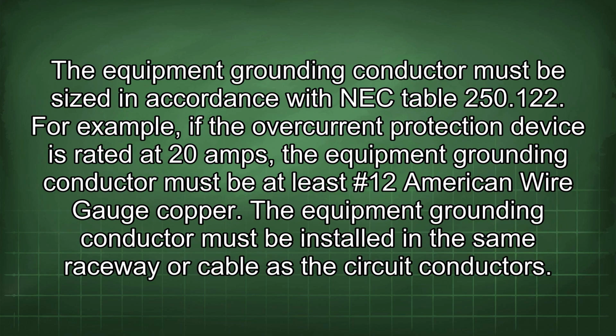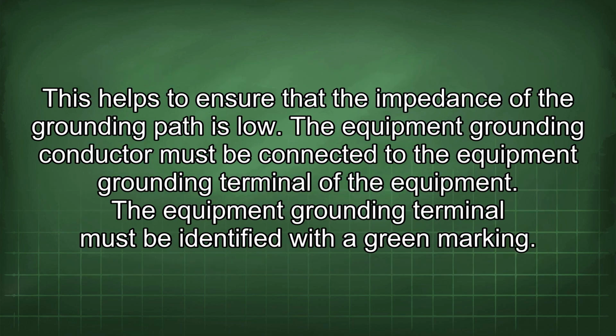The equipment grounding conductor must be sized in accordance with NEC Table 250.122. For example, if the overcurrent protection device is rated at 20 amps, the equipment grounding conductor must be at least #12 American wire gauge copper. The equipment grounding conductor must be installed in the same raceway or cable as the circuit conductors. This helps to ensure that the impedance of the grounding path is low.